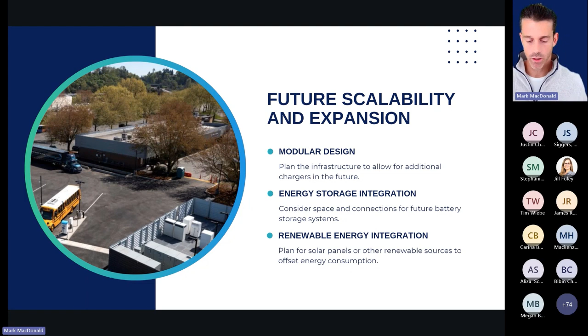Another big one is future scalability and expansion. Does the charger have a modular design? Us and others - if you buy a 120 kilowatt from us, you can upgrade that down the road to 180 kilowatts. We use a rack-based power distribution system, so you can actually increase the output, the DCFC output, on our chargers. So is it a modular design? Can I upgrade it? Do I need room for energy storage systems to supplement or complement the available grid connection? Do I want to do some renewable energy integration down the road, which is now becoming a standard of the OCPP protocol? So all future scalability and expansion considerations.